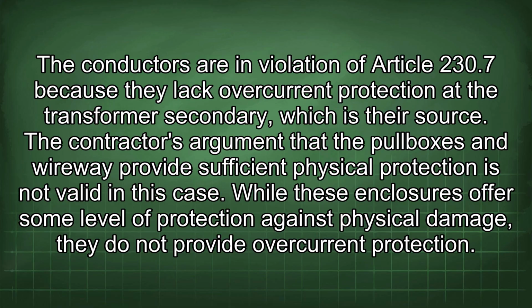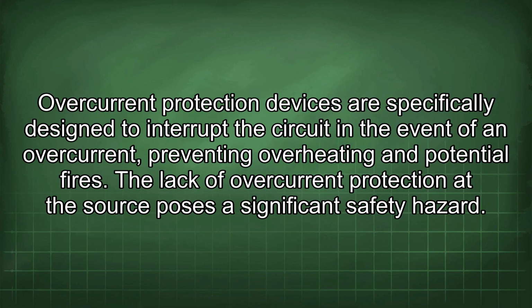The contractor's argument that the pullboxes and wireway provide sufficient physical protection is not valid in this case. While these enclosures offer some level of protection against physical damage, they do not provide overcurrent protection. Overcurrent protection devices are specifically designed to interrupt the circuit in the event of an overcurrent, preventing overheating and potential fires. A lack of overcurrent protection at the source poses a significant safety hazard.